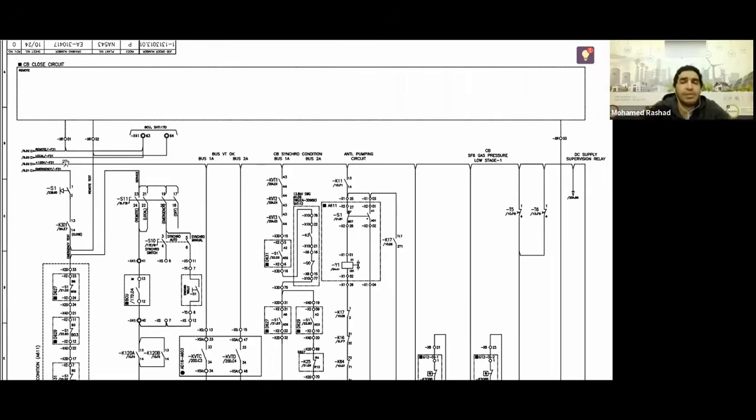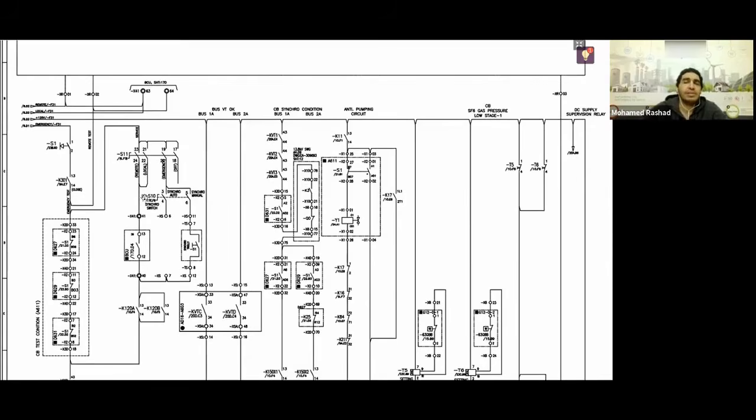But in some emergency cases, communication might have failed and you are not able to see the station. So you can come to the station yourself. Through the cells themselves, you can give close and open commands to the components you have, like the disconnector switch, the earth switch, the breaker, and so on. This is called an emergency, not an emergency in the sense that you are in a critical situation and it brings electricity from the next station. No, don't let your mind go down that path at all.